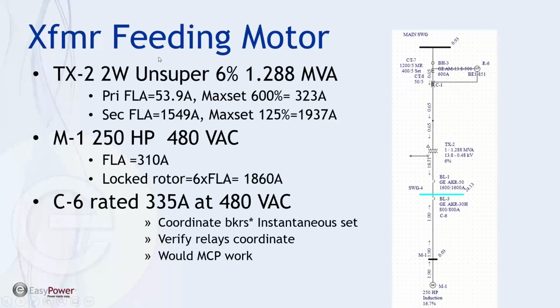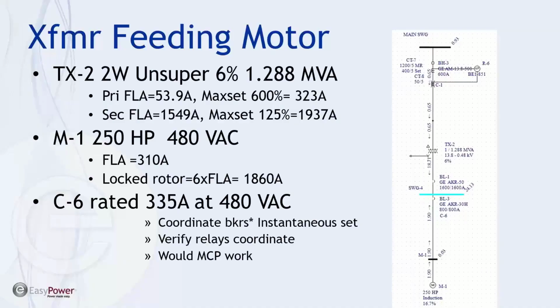Okay, so next we want to look at the other end of the drawing, which is a transformer feeding a motor. And so again, the upstream protection is going to be for the transformer protection itself. The downstream breaker, we can see it here, will be protecting the motor itself, and then any cables that may be sensitive to the max current. So we want to coordinate the breakers first, with the last one having an instantaneous trip, and then verify that the upstream relays coordinate. And so this is main switchgear down to 250 horsepower motor M-1.